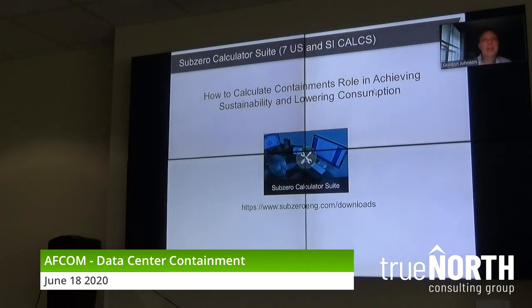This was a simple case study, but it doesn't matter if it's a small data center, a medium, or a really, you know, high HPC, large scale. You're going to save a lot of money in a data center when you put in containment. Because you're going to separate that cold supply air from the hot exhaust air, and only then can you start doing that cooling optimization. You're going to be able to say, I want 75 degrees supply air temperature getting to my IT equipment, so I'm going to set the supply air for my cooling units at 75. I can have confidence that's the temperature they're going to get. And you're going to be in control of that because, again, you've separated the cold supply from the hot exhaust.